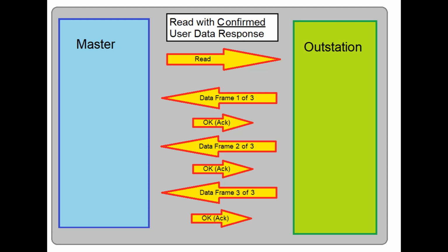Confirmed user data was included for use on noisy communication lines, where it is possible a message would not arrive as sent. If the line is very noisy, then confirmed user data provides a means to identify errors and recover. There are other ways to detect errors and recover, but those are in the application layer and do not come into play until all frames are sent.